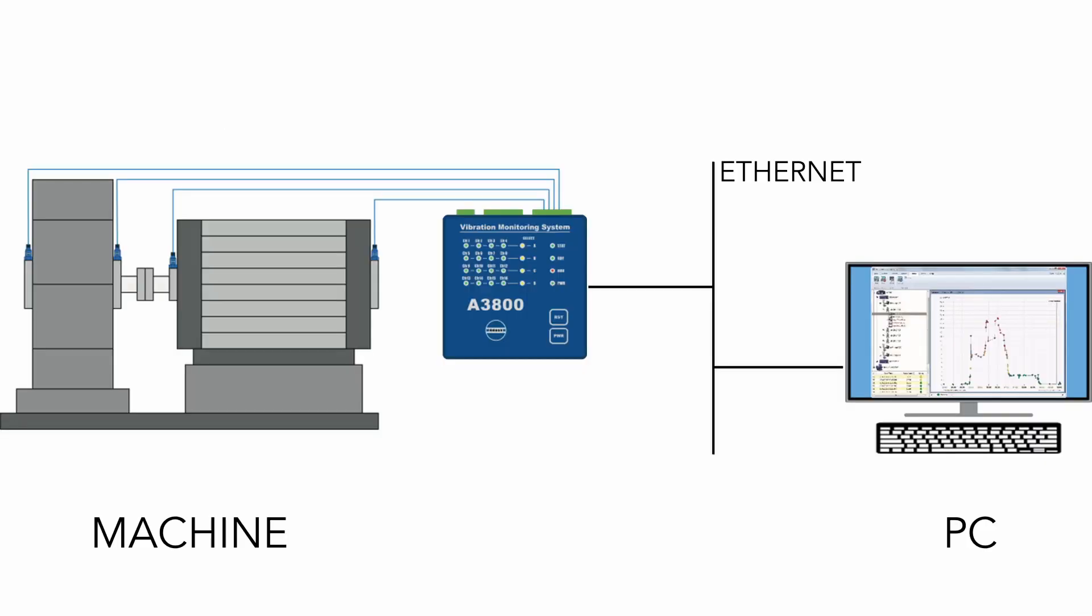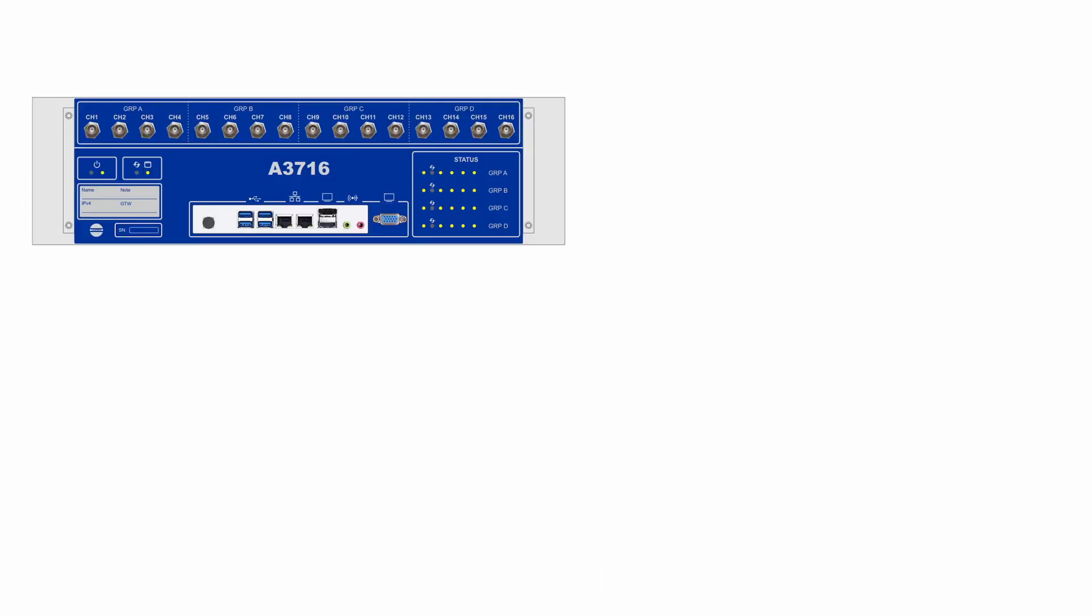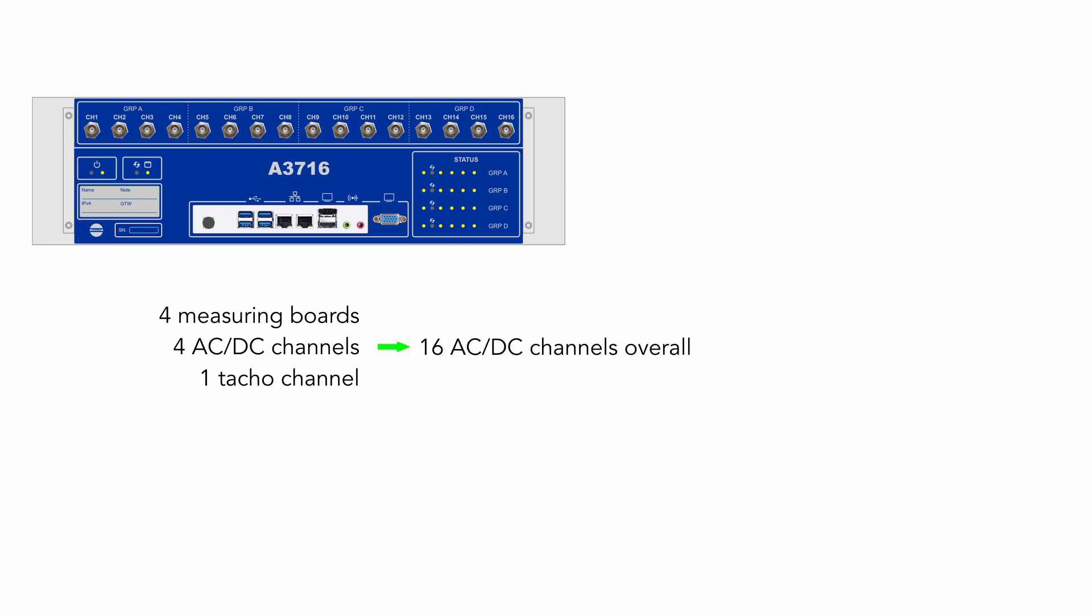Online monitoring systems are used for reading the vibration on machines continuously. We use devices we call online units. We have two types of them. First type is online unit A3716. This unit contains four measuring boards. Each of these boards has four AC channels, four DC channels and one tacho channel. It means that online unit A3716 has 16 AC channels, 16 DC channels and four tacho channels overall.